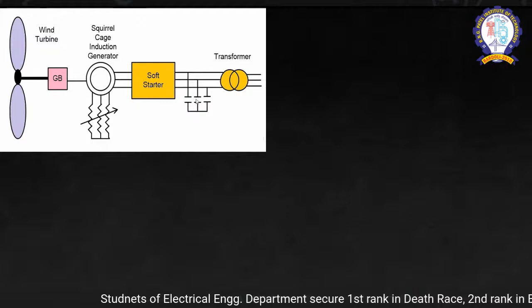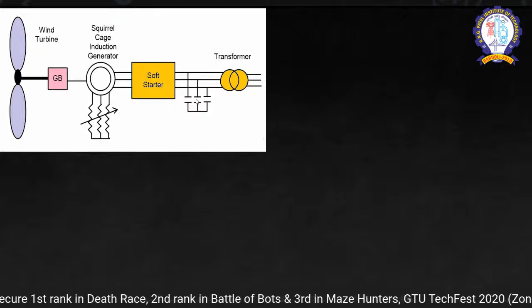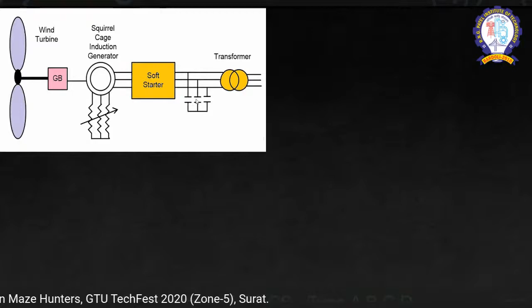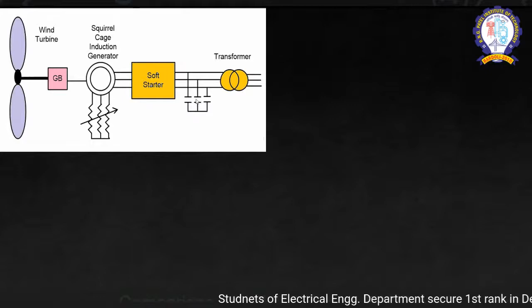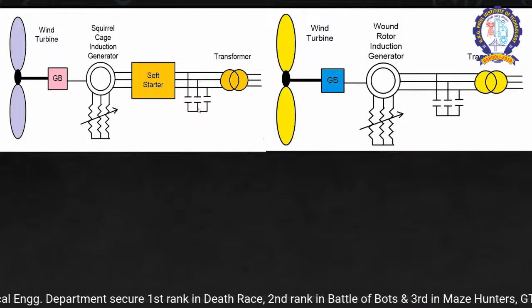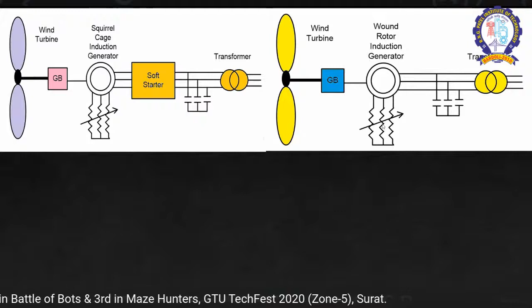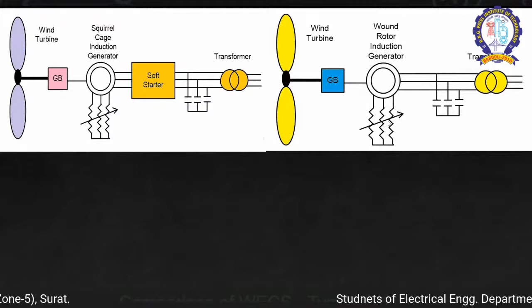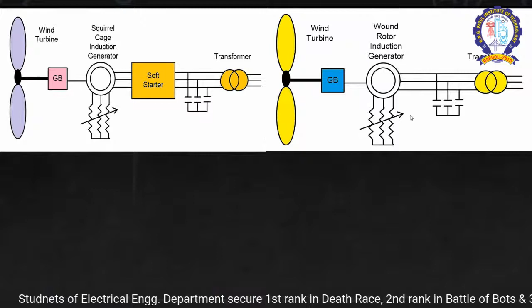Otherwise, this induction generator will not feed electrical power into the grid, and the gearbox is of massive gear ratio because we need to turn our rotor at super synchronous speed. This could be achieved in both ways. If you go with the wound rotor induction generator with slip rings, the soft starter is not required, because the torque is already controlled using the wound rotor, where the rotor circuit is interfaced with a 3-phase resistance.